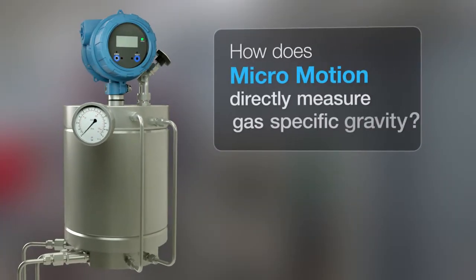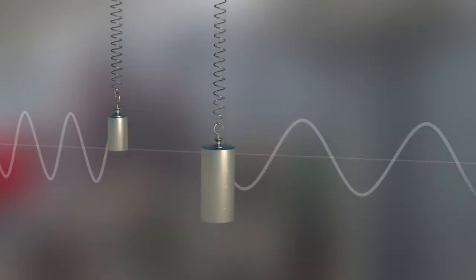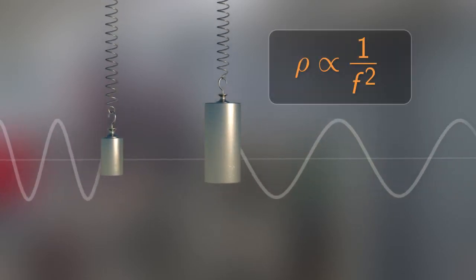How does Micro Motion directly measure gas-specific gravity? The Micro Motion Specific Gravity Meter, or SGM, builds off the foundation of vibrating element gas density meters, using the principle that frequency of vibration is inversely proportional to density.